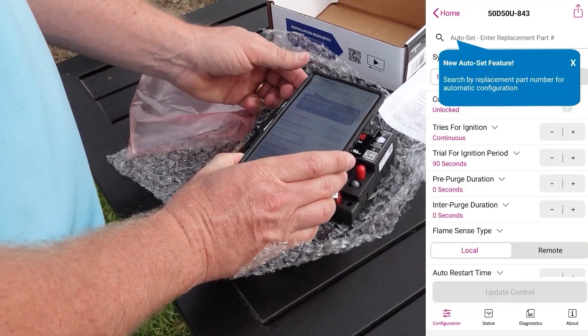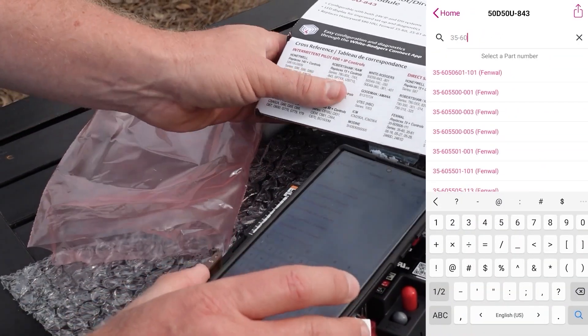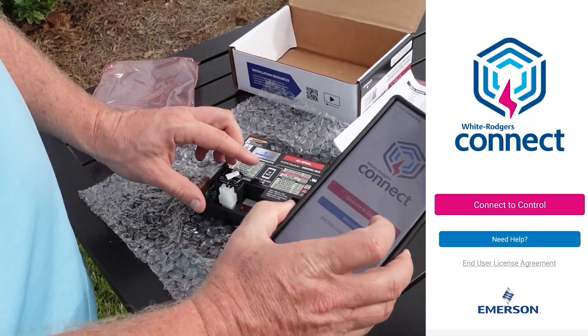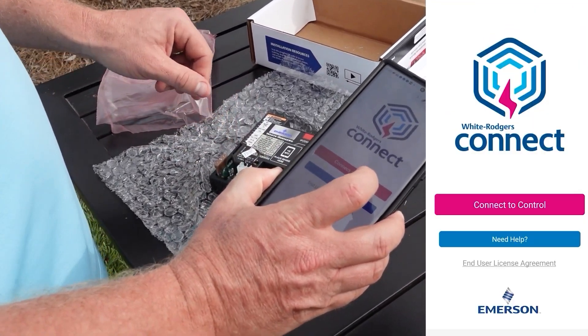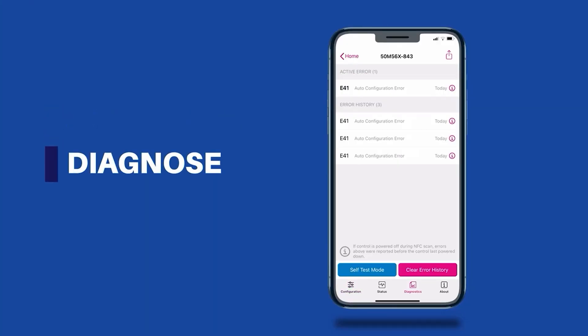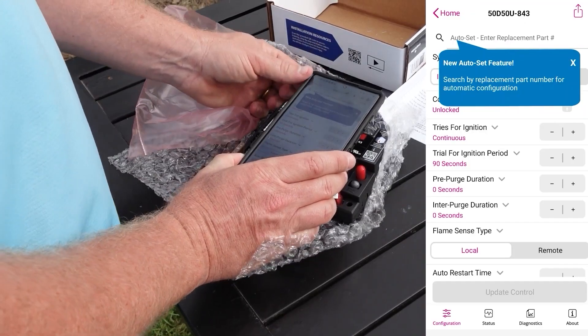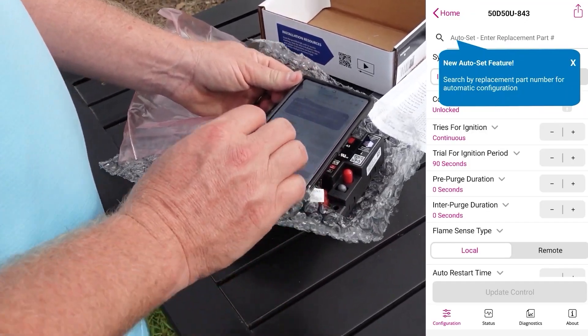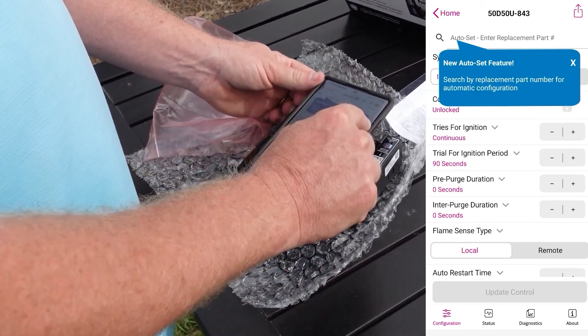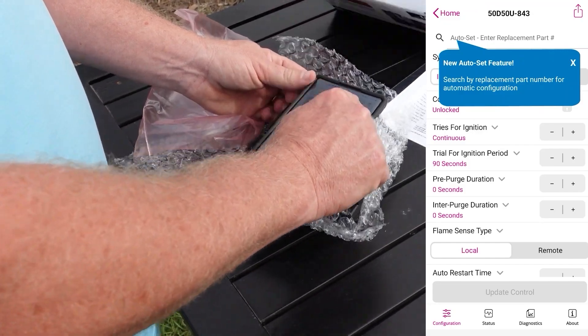You can use the auto-set feature to type in the OEM part number to auto-configure to OEM settings. If you wish, you can also make adjustments. The White-Rodgers Connect app uses NFC, just like a credit card reader — no registration, login, cell service, Bluetooth, Wi-Fi, any of it. You just literally tap, and you can update the control after you adjust those settings with another tap. Super easy. It uses the power from your device, so the control does not need to be powered to make this work.